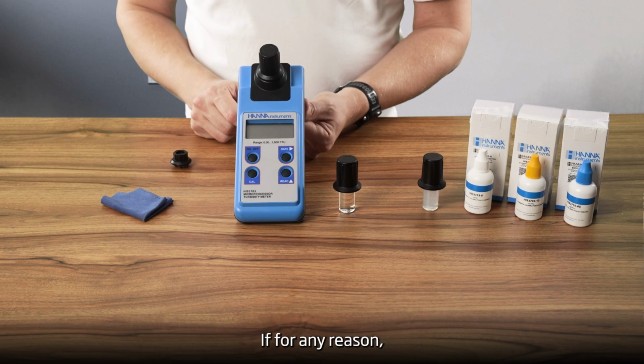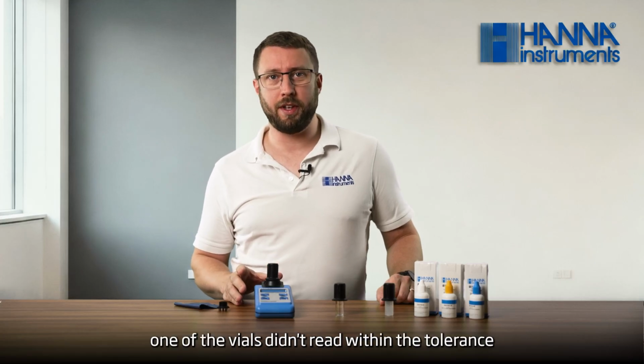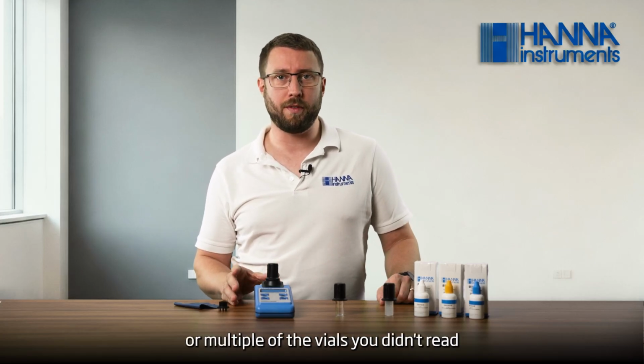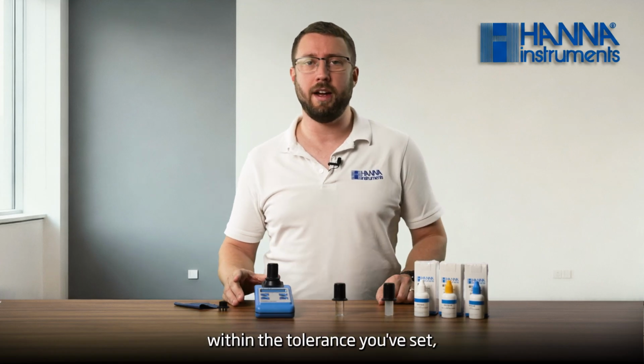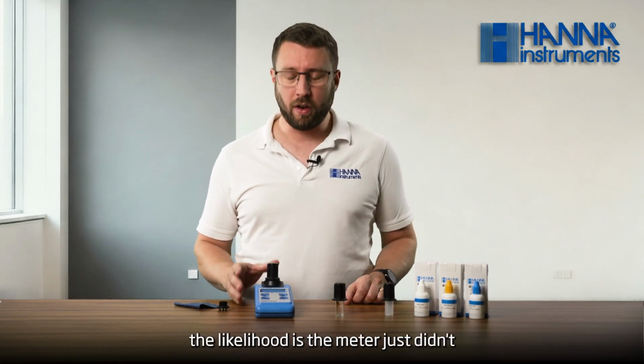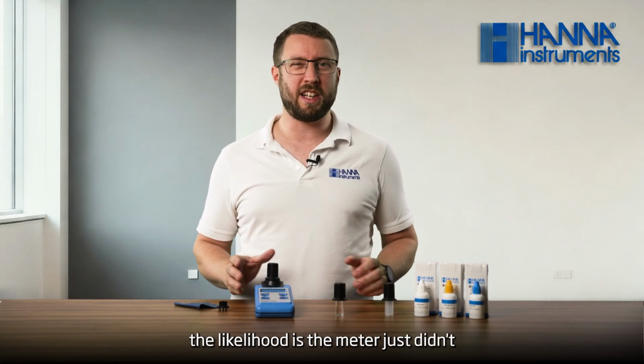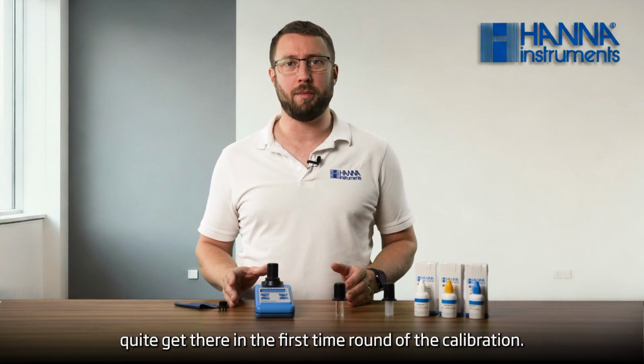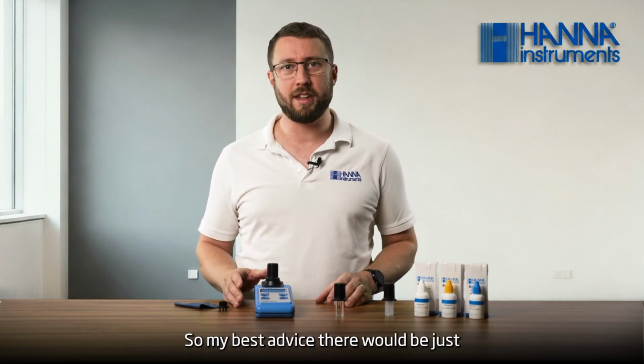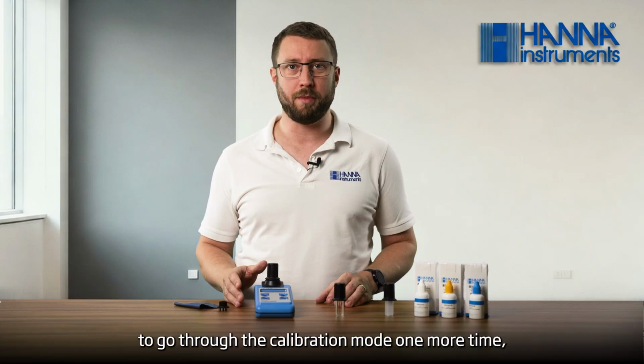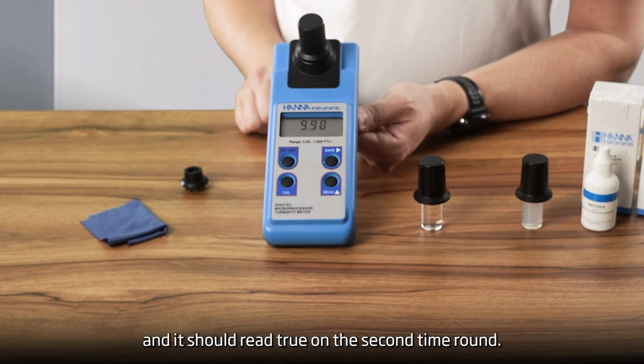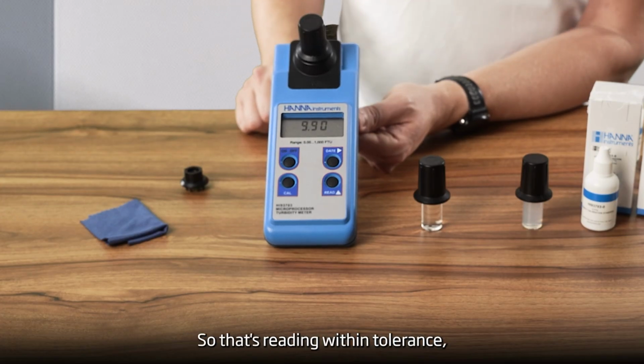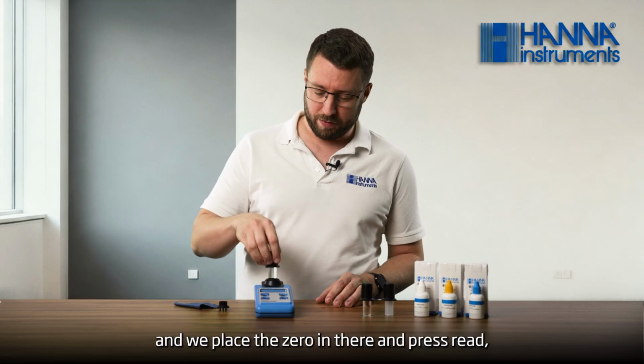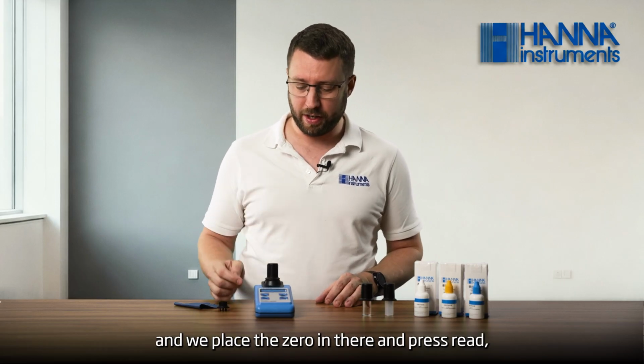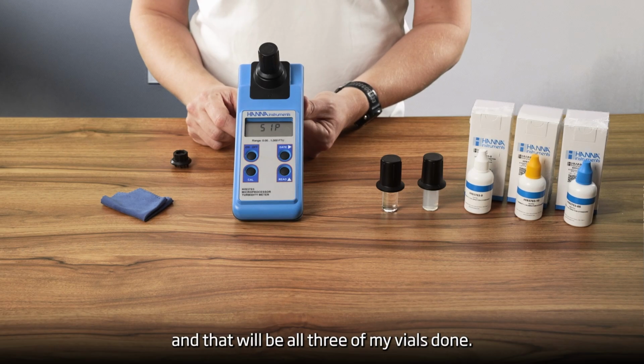If for any reason one of the vials didn't read within the tolerance that you've set, or multiple of the vials didn't read within the tolerance you've set, but they are close, the likelihood is the meter just didn't quite get there in the first time round of the calibration. So my best advice there would be just to go through the calibration mode one more time, and it should read true on the second time round. So that's reading within tolerance, and we place the 0 in there and press read, and that will be all 3 of my vials done.